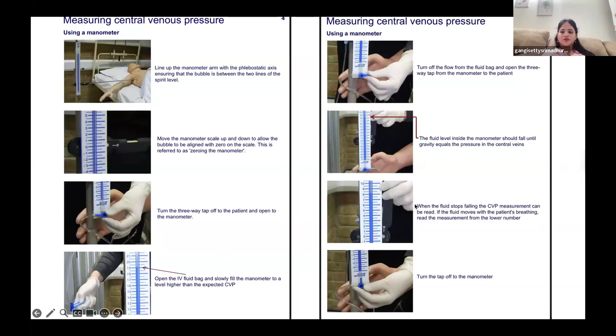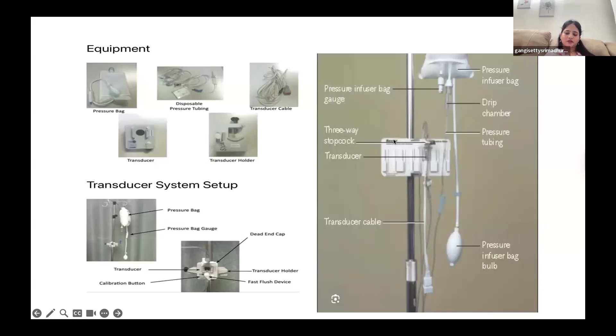So that value is the CVP of the patient, which can be measured. And we can turn off the manometer. Coming to the transducer, these are the equipment present in the transducer: one is a pressure bag, disposable tubing, transducer cable, the transducer itself, and the holder. These are the parts that are primarily important and have to be considered. We have to set up the transducer before preparing the patient for the insertion.